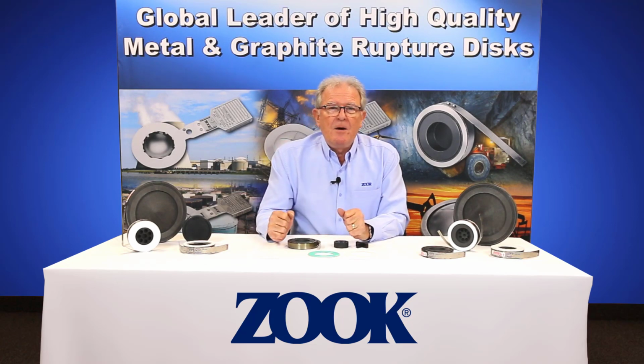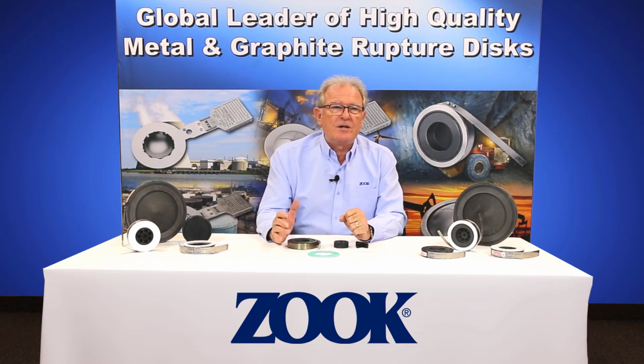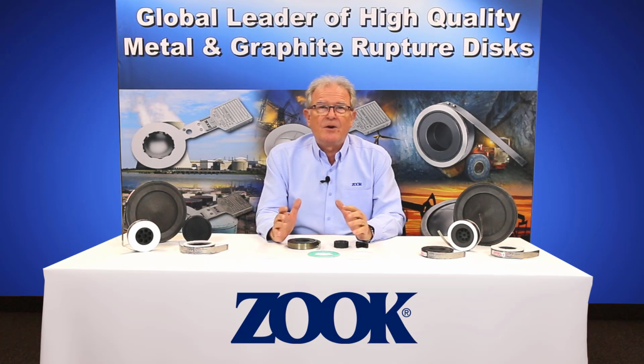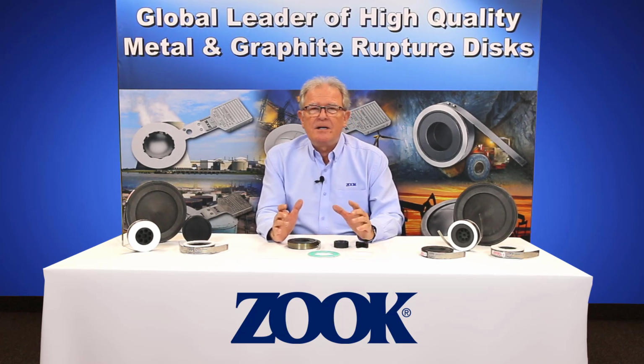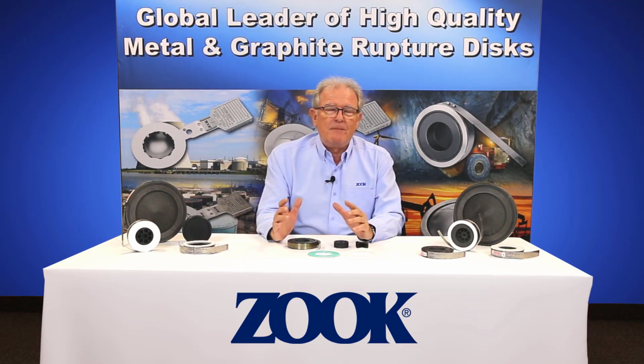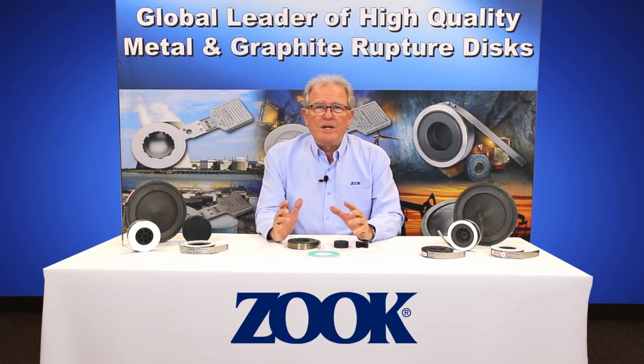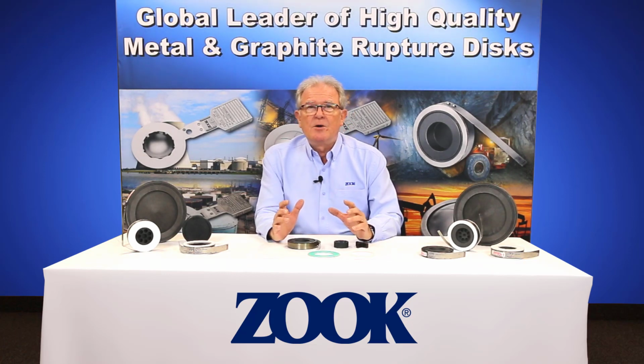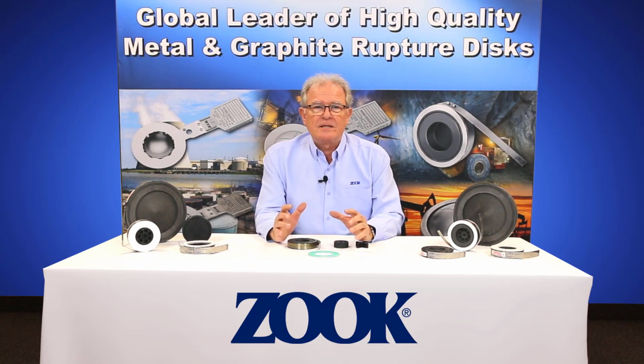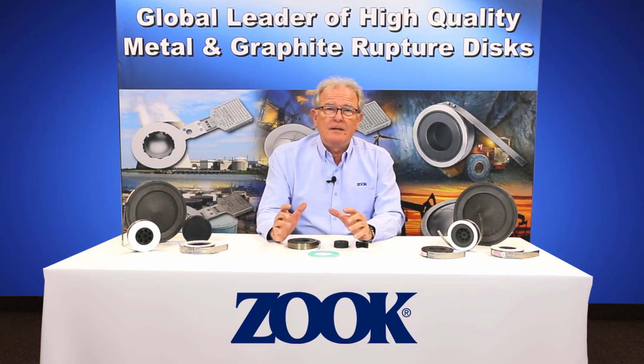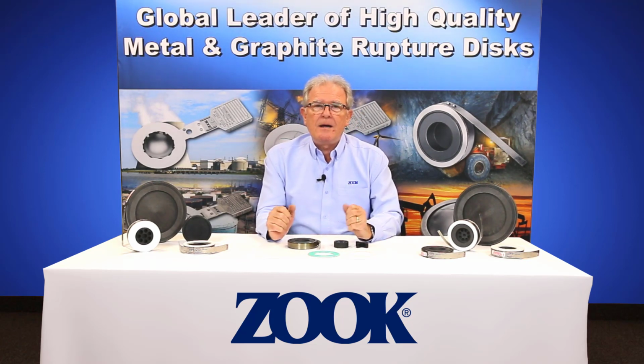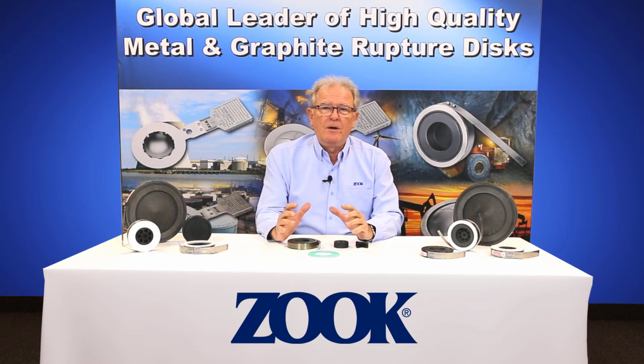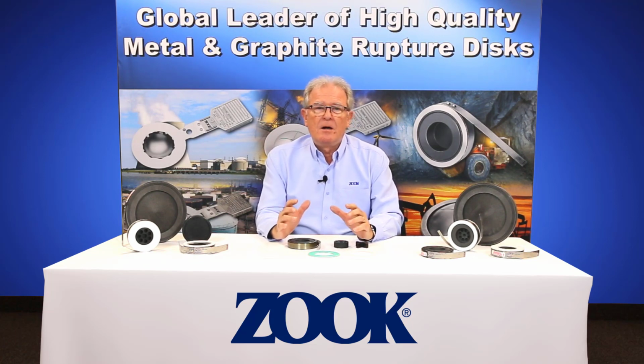Now I'm hearing you say, why use graphite as a material of construction for a rupture disc? Now that's a very good question. In the early days of rupture discs, the only materials that were being used were metals. Metal has a high tensile strength, which meant that only medium to high pressures could be created for rupture discs. Now with graphite, with a low tensile strength, we can now apply this material for low pressure requirements on reactor and storage vessels needing a low pressure relief device.